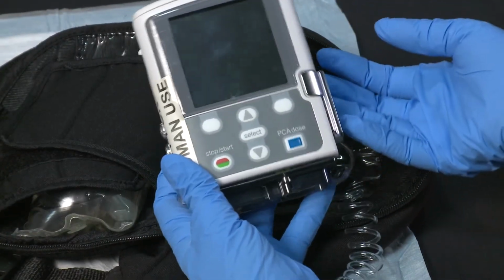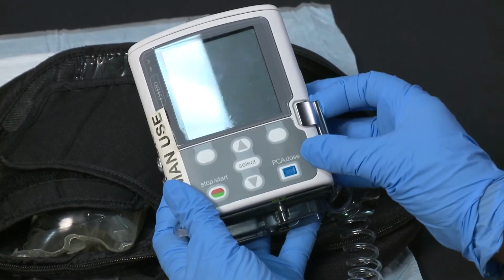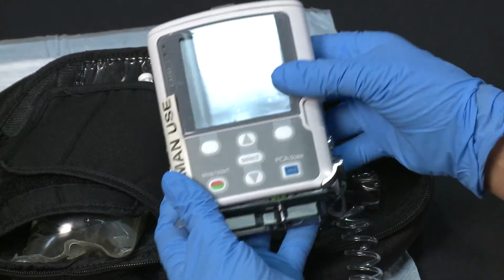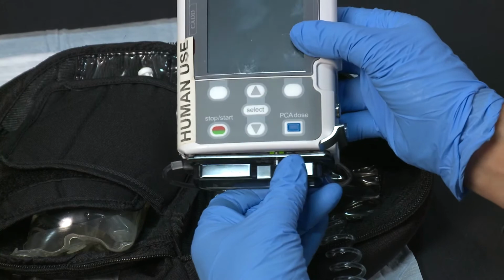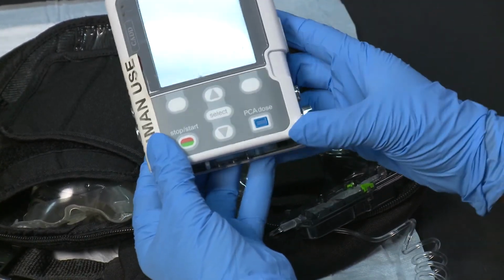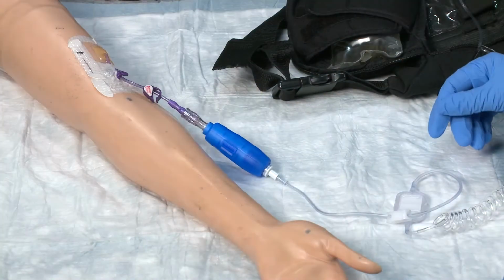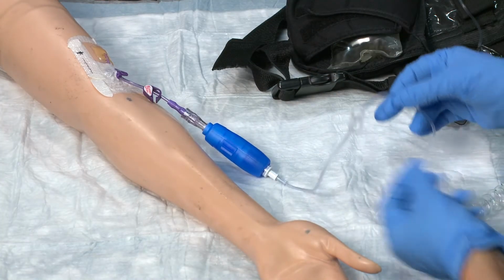Next, you need to release the cassette. Push down on the cassette latch until cassette detaches. Remove the cassette, which holds the tubing that is attached to the empty bag. Now you are ready to disconnect.